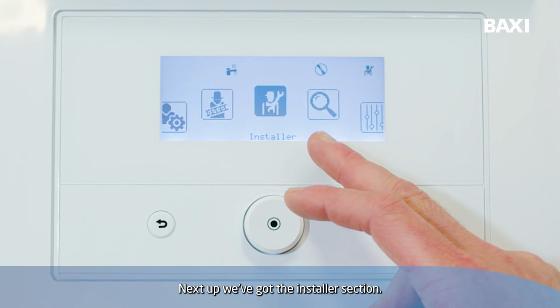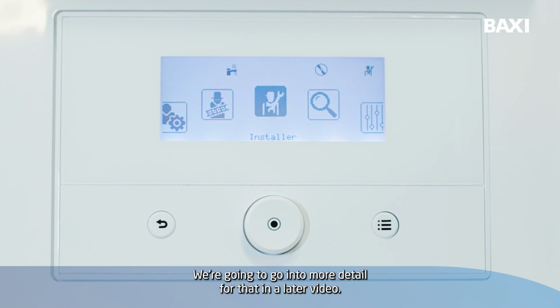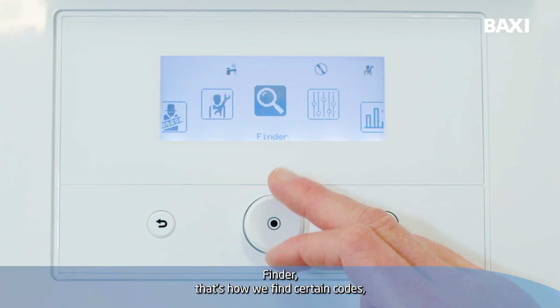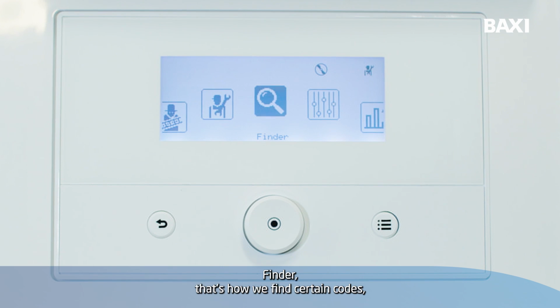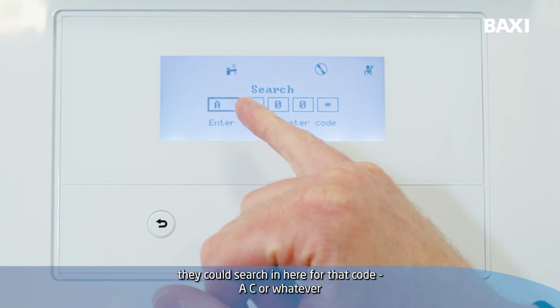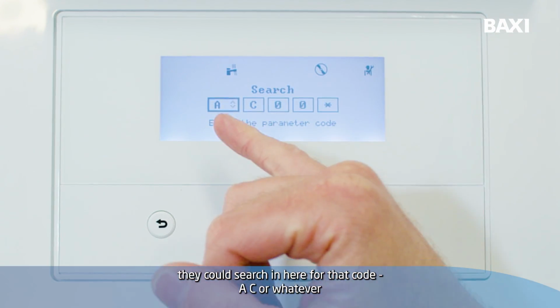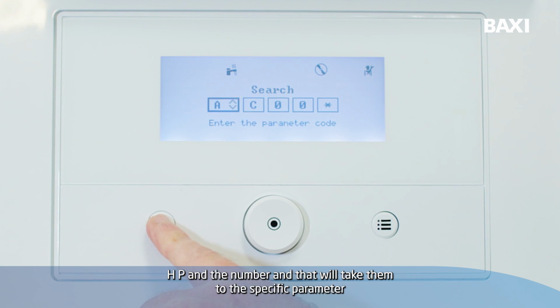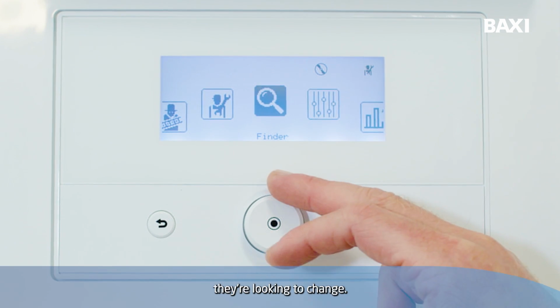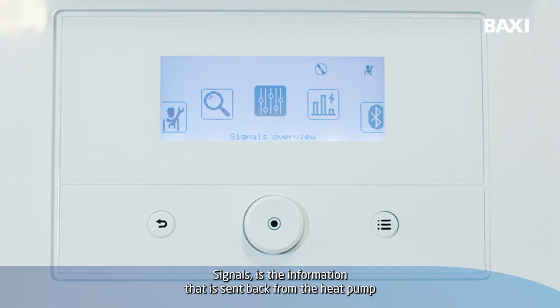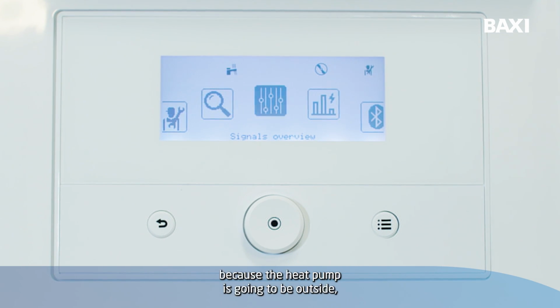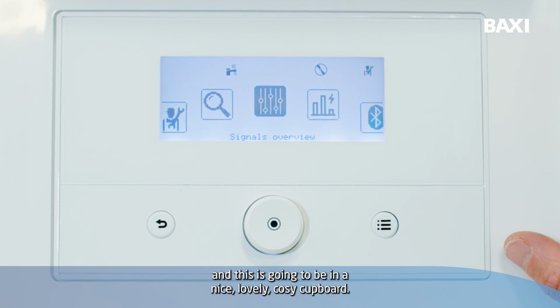Next up, we've got the installer section. We're going to go into more detail for that in a later video. Finder, that's how we find certain codes. If the installer, for example, wanted to change a certain parameter, they could search in here for that code, AC or whatever, HP, and the number, and that will take them to the specific parameter they're looking to change. Signals is the information that is sent back from the heat pump to the controller for us to view what the heat pump is doing, because the heat pump's going to be outside and this is going to be in a nice lovely cozy cupboard.